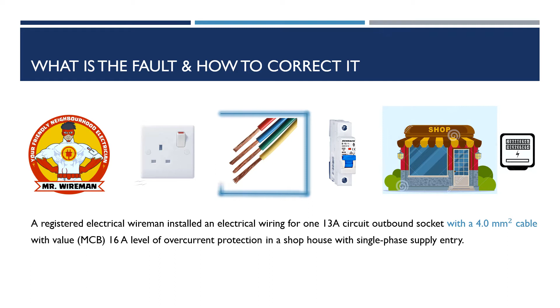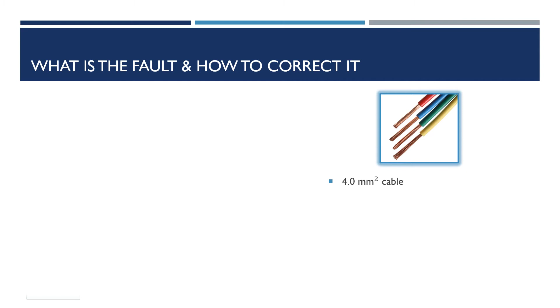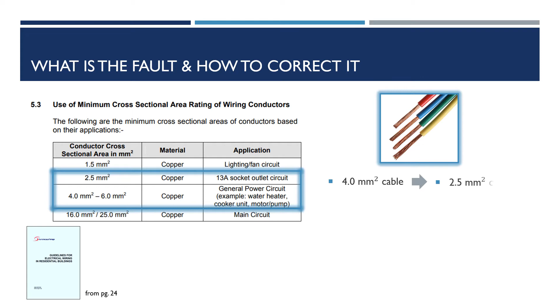The 4.0 mm square cable. Now, we have the 4.0 mm square cable. From page 24 of the guidelines, we get this: the minimum cross-sectional areas of conductors based on their applications. For a 13 ampere outlet circuit, we use the 2.5 mm square cable, and that is the correct size.